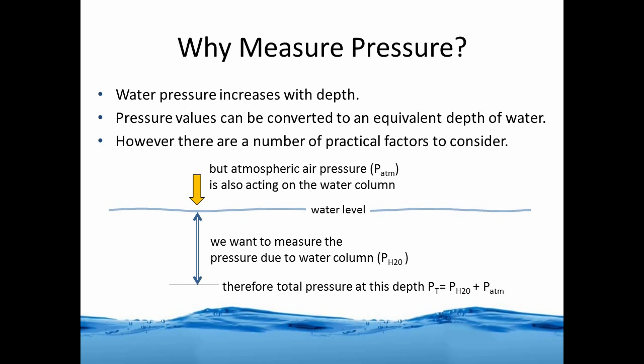Let's look at this diagram. Water pressure obviously increases with depth — we've all experienced it diving in pools where our ears feel more pressure as we dive deeper. These pressure values can be converted to an equivalent water depth value; however, there are a number of practical factors to consider. Looking at the diagram, you have two sets of arrows: the blue arrow represents what we want to measure — the pressure due to the water column at a particular depth below the water level. But we also have the effect of atmospheric air pressure acting on the same water column, so the total pressure at depth is the combined water plus atmospheric pressure.